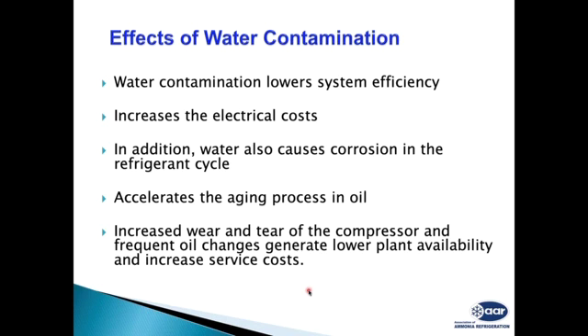Also, with water in the system, it starts corroding the equipment and material, because most of the time we use steel components in the refrigeration system. The corrosion starts because air is entering the system, bringing nitrogen, oxygen, then water into the ammonia and the metal parts, causing a lot of corrosion. Secondly, when this water mixes with the oil, it starts the aging of the oil. Aging of the oil means the oil quality will continuously deteriorate. The oil's capacity to function as required will deteriorate, which will increase wear and tear of the compressor. We need to change the oil frequently, so oil consumption goes up.